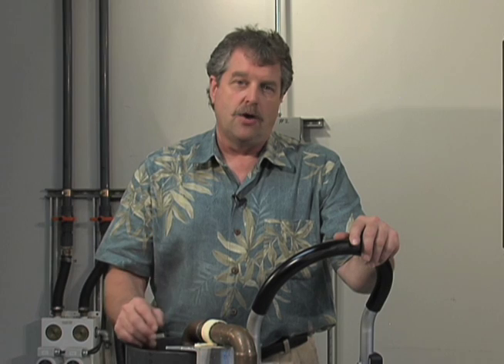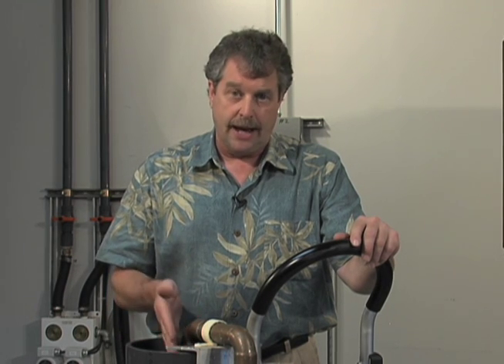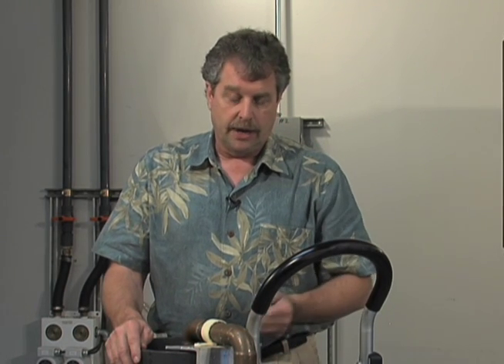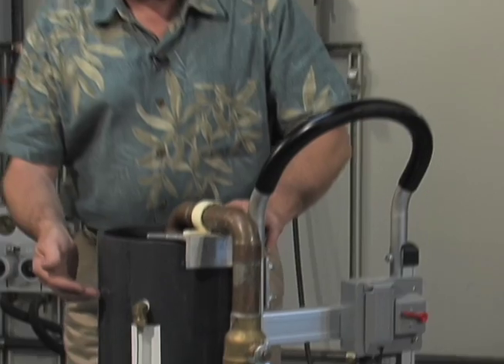So we've allowed our system to circulate for a while now, so if we've moved any air out, we've been able to dislodge it and dissipate it out of our reservoir. I've actually done several more deadheading procedures, so let's see if we've moved any air out of the system and check our water level in the sight glass.